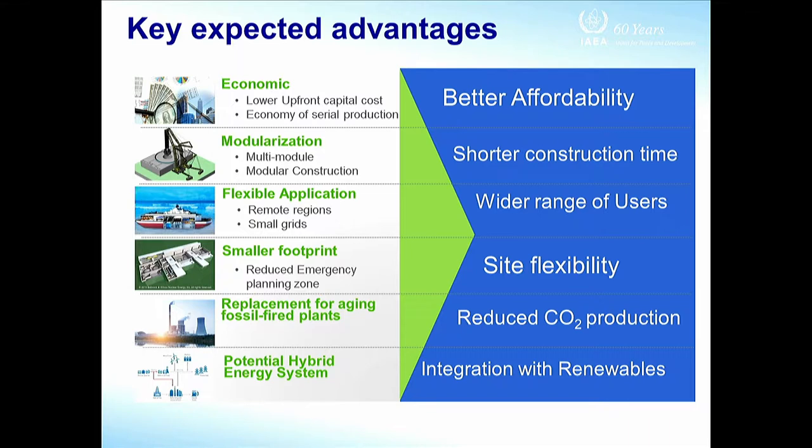And here is a very important conceptual point. You know that with the new safety approach, even promoted by the IAEA, the levels of defense are five, not four. Okay? There is a fifth level of defense in depth, which is emergency preparedness and response. So it means that in any case, the operators and all the systems should be ready to face any kind of emergency situation, including a severe accident. The fact that there is an option with SMR, and this has also already been clarified even for Gen 4 reactors, the fact that in principle you can at least reduce the EPZ, if not eliminate it, depends very much on the interpretation of practical elimination of some severe accident conditions.